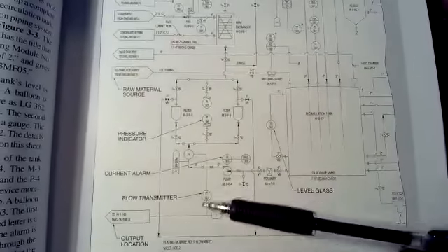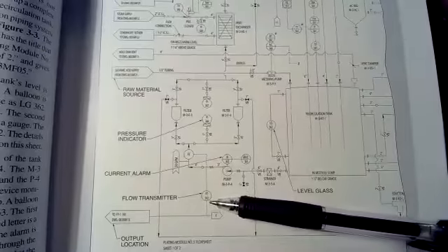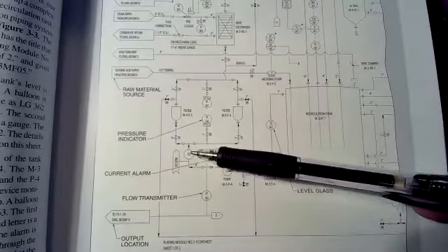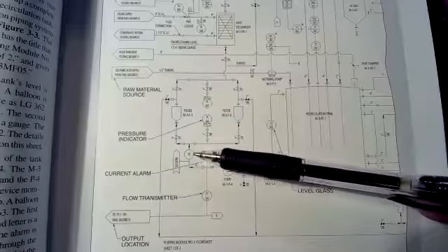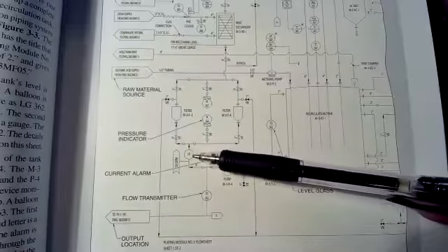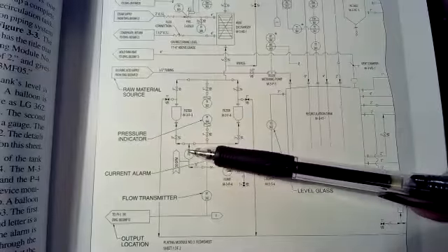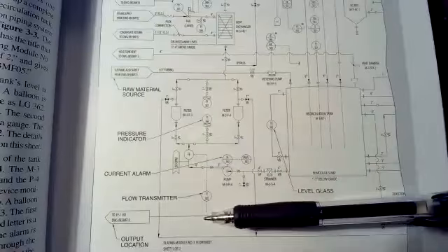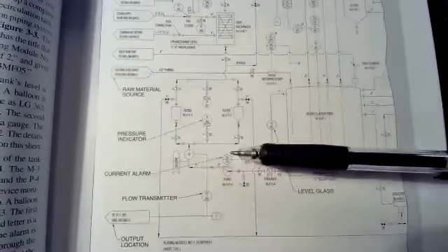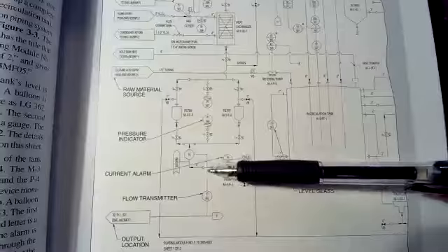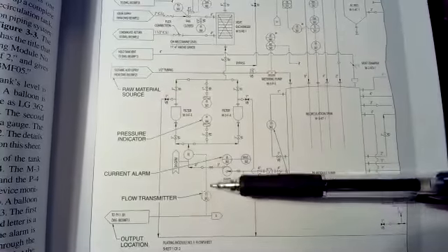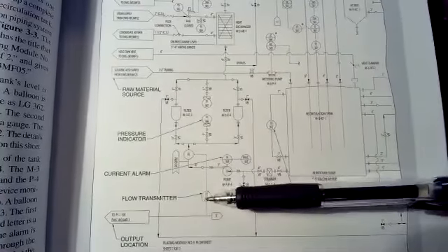You have a flow transmitter, which is usually linked to a flow element. An element is what you're actually, that's your meter, that's your electronic meter on the flow of a liquid. In this case, it's sitting right on top of that pipe coming out of that pump. So I'm measuring the flow out of that pump, and I'm sending a signal to a transmitter. This is a dotted line, so it's probably an electrical signal.